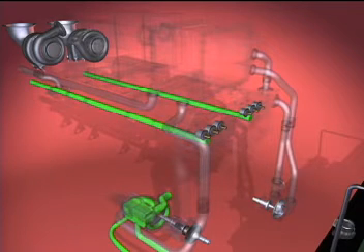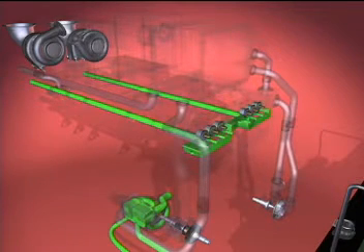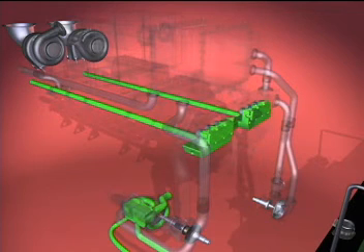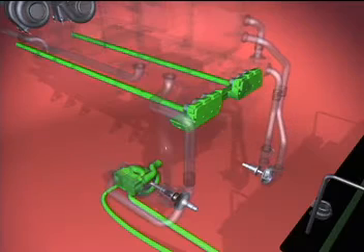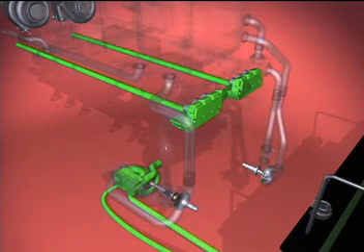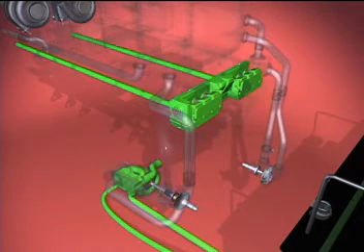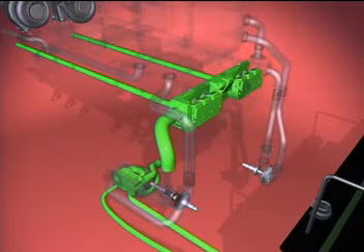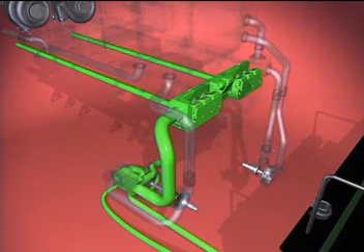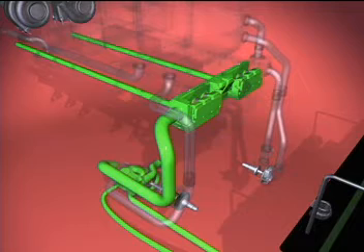Coolant in the thermostat housing circulates around the sensing bulbs of the 6 high-temperature engine thermostats. When the coolant at the engine thermostats is below the thermostat modulating range, the thermostats are closed, allowing the coolant to flow through the center of the thermostats. The coolant then flows out the bypass connection on the right end of the housing. The coolant passes through the bypass line and back to the inlet of the water pump.